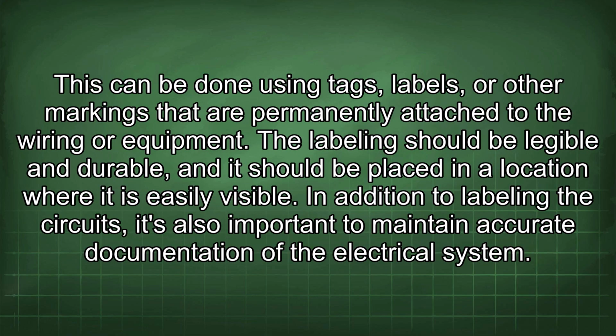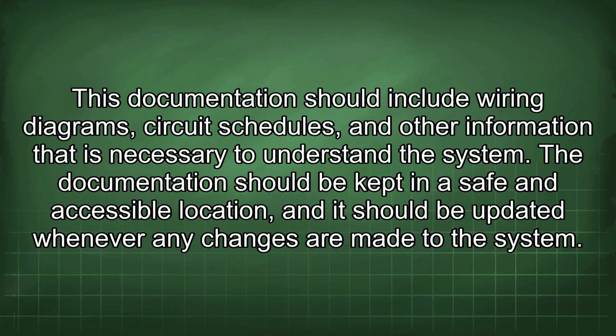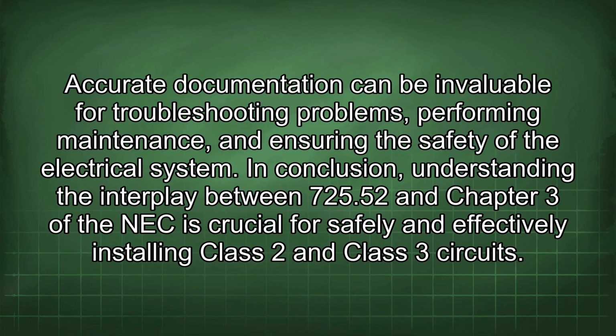This can be done using tags, labels, or other markings that are permanently attached to the wiring or equipment. The labeling should be legible and durable, and it should be placed in a location where it is easily visible. In addition to labeling the circuits, it's also important to maintain accurate documentation of the electrical system. This documentation should include wiring diagrams, circuit schedules, and other information that is necessary to understand the system. The documentation should be kept in a safe and accessible location, and it should be updated whenever any changes are made to the system. Accurate documentation can be invaluable for troubleshooting problems, performing maintenance, and ensuring the safety of the electrical system.